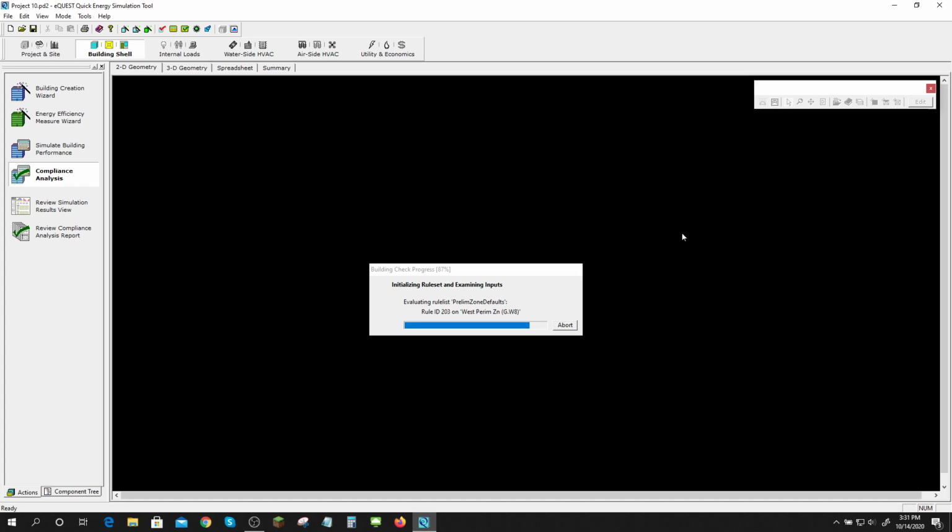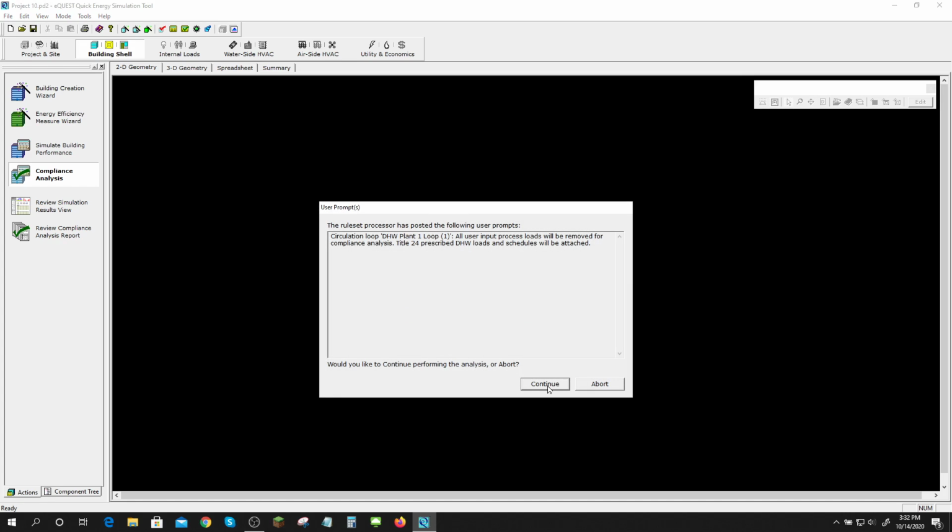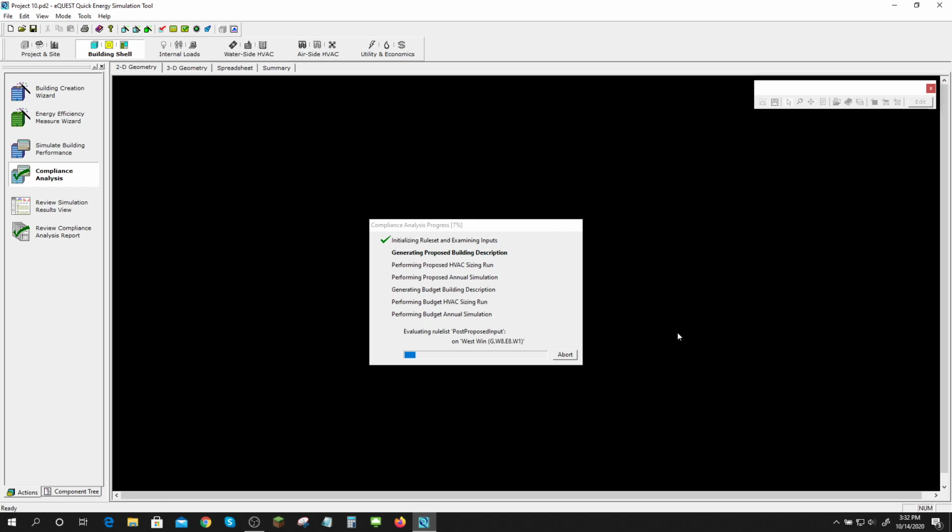So you see, though, we're going to have taken maybe 10 or 15 minutes, and we'll really locked in on some things. We'll know that the building's shape and its orientation and the amount of windows are fine. We'll know that we need to specify a certain efficiency on the mechanical components. They call that the HVAC is the mechanical components. We know that we're going to have to specify a certain motor efficiency for the fans, and that we're going to have to probably specify Energy Star rated lighting and equipment in the place.